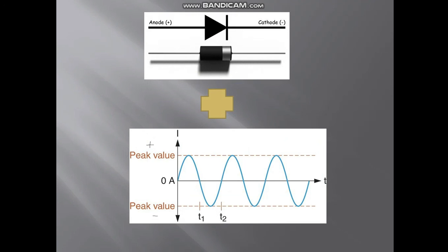And that is where the rectifier will jump in. As stated earlier, the rectifier is one of the components of the high voltage generator. So before the high voltage generator transmits electricity towards the X-ray tube, it must first undergo some transformation so that the voltage traversing from positive to negative cycle will only traverse on the positive cycle.